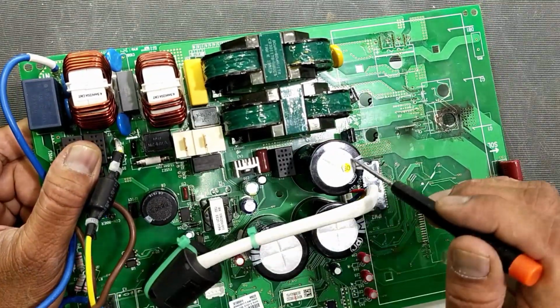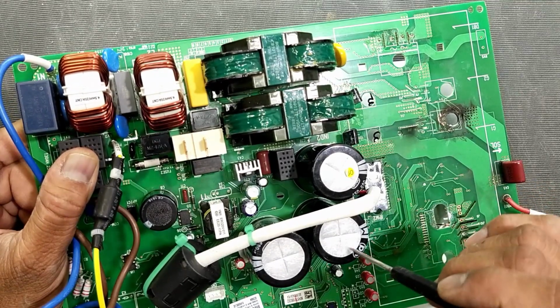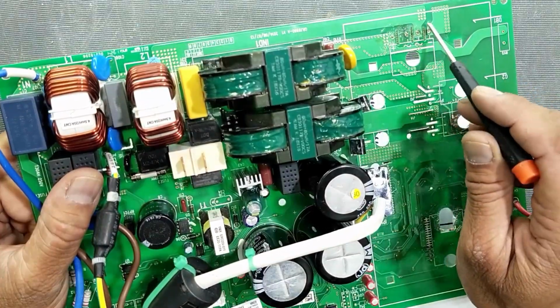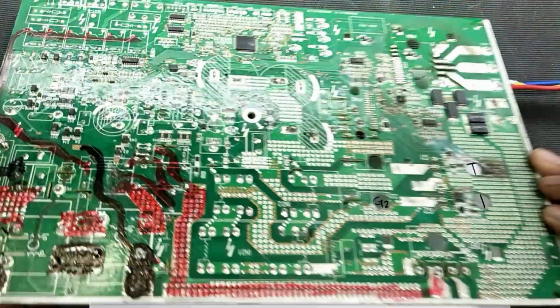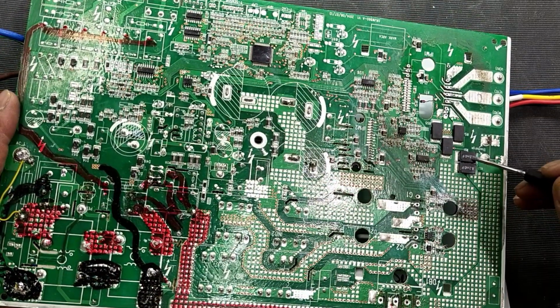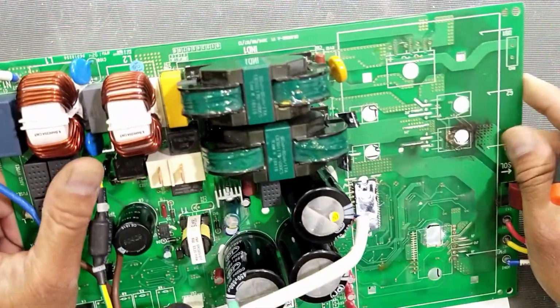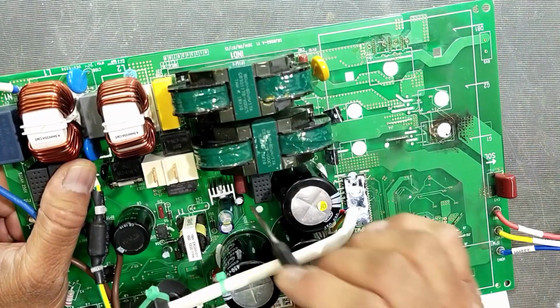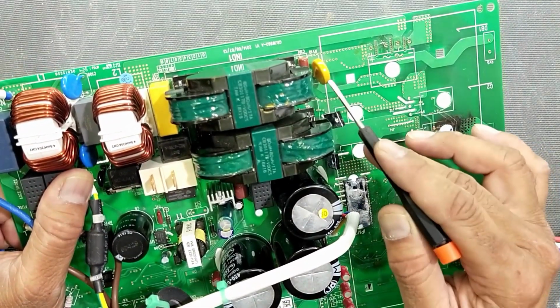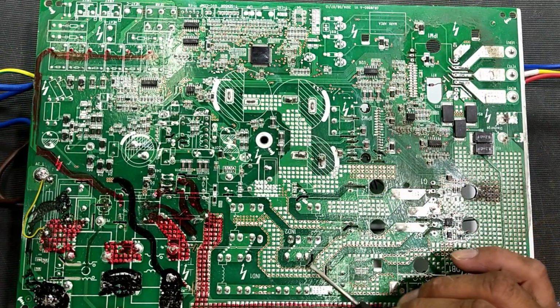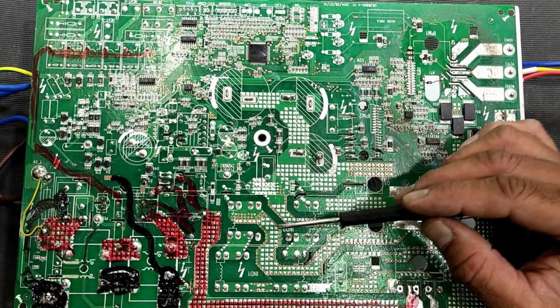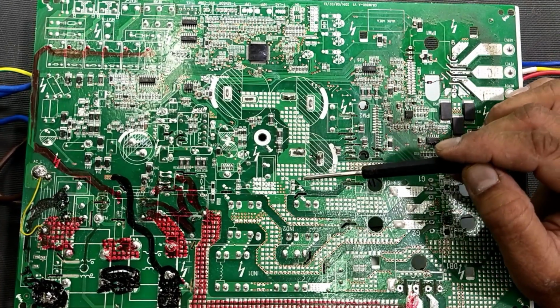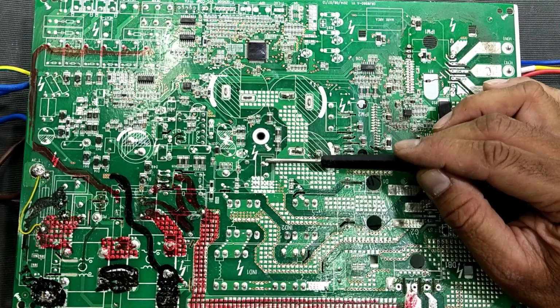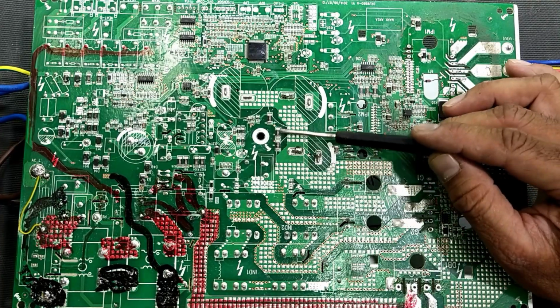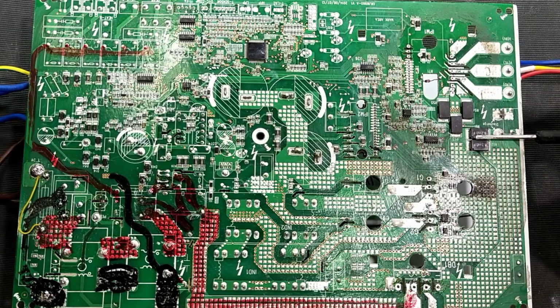If this MOV becomes shorted due to over voltage in this section, the capacitor will not charge and our bridge rectifier might be damaged, and in that case we will get a high current protection or overcurrent error. If any component, IGBT or diode, is damaged, we will get an overcurrent issue and also an under voltage issue, because when these components become short circuit, they draw more current than the rated value, since normally they are open. But if any component becomes short circuit, it will draw more current, causing the voltage to drop in the DC rail, generating overcurrent and under voltage.